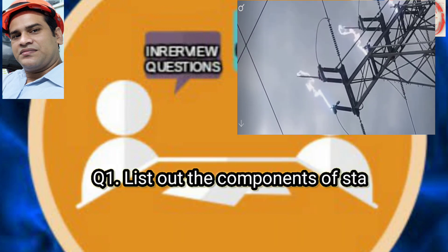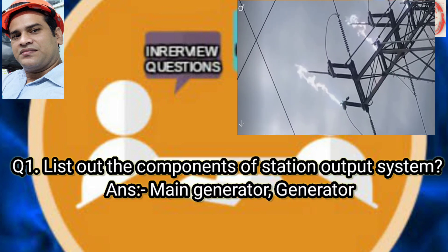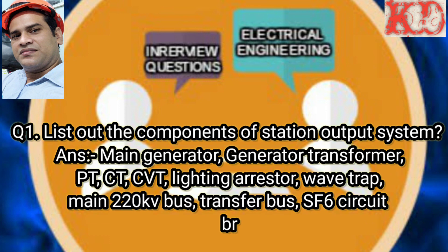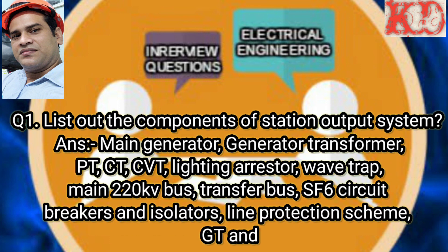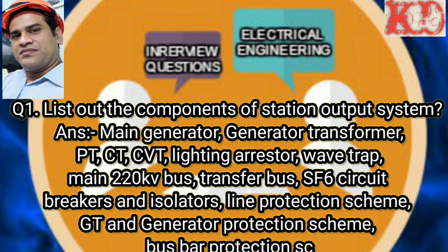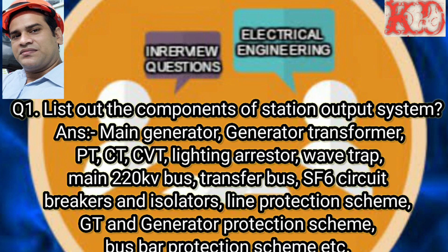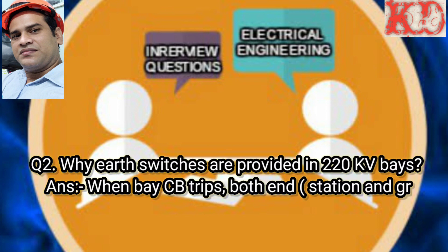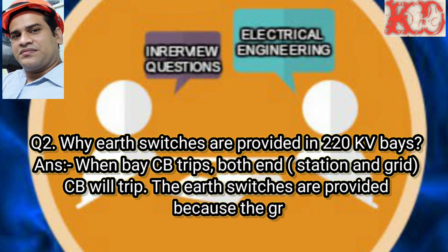Question number 1: List out the components of a station output system. Answer: The components are main generator, generator transformer, PT, CT, CVT, lightning arrester, wave trap, main 220 KV bus, transfer bus, SF6 circuit breaker and isolators, line protection scheme, GT and generator protection scheme, and bus bar protection scheme.